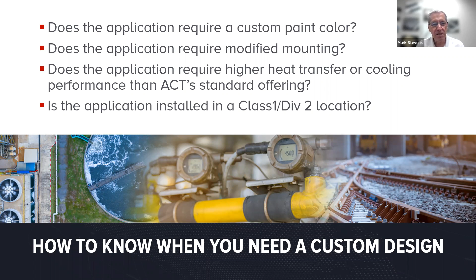And then installation and operational considerations. When you're looking at applying this product, which one do you pick? Is it above ambient or sub-ambient? You always have to consider: is the temperature inside the cabinet hotter than the outside? If it's hotter on the inside of the cabinet, you can probably get away with using an above ambient cooler. As Devin was talking about with the air conditioned products, the outside of the cabinet is going to be hotter than the inside, so you're going to have to cool it with an air conditioner.